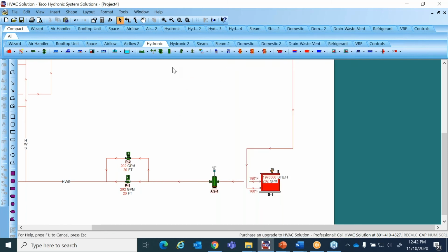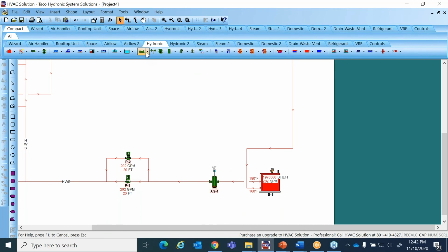So please consider that. Notice when I drop this in—let me undo that. When I dropped it in, watch what happens when I hit redo—I love playing with the redo button—it went right back up to 20 feet. So it added 6 feet of head loss for that component once I dropped it in on the screen.